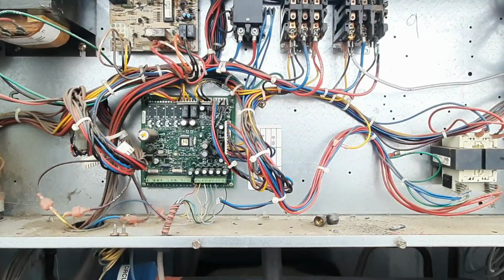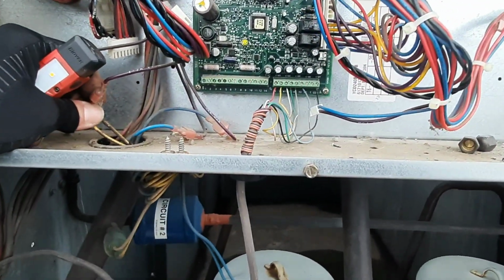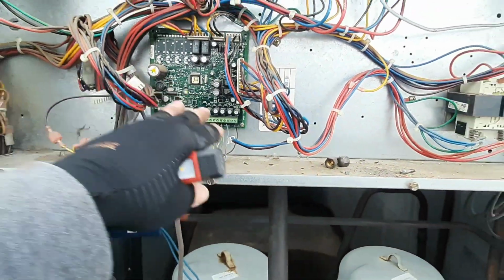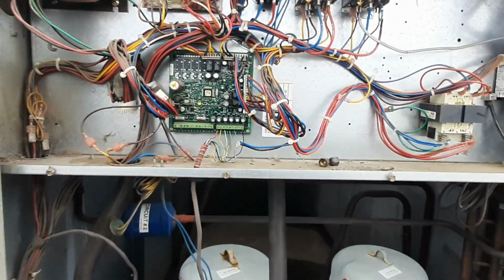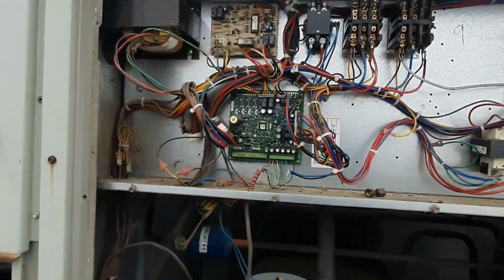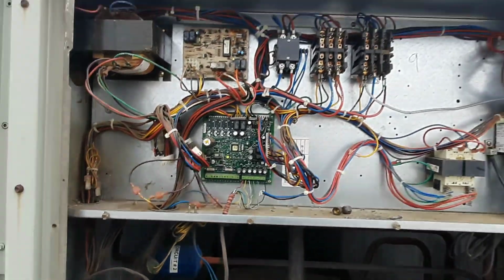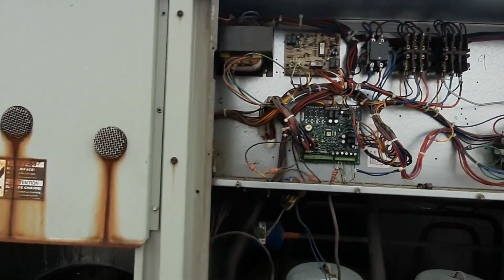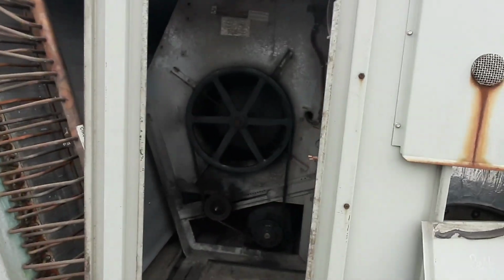And see where we go from there. Like I said, if nothing else, it's a big warehouse, we can leave a blower running. We'll just pull all the rest of our low voltage wires, that way we don't get a lockout, because for whatever reason, the lockouts seem to be causing the blower contactor to chatter.